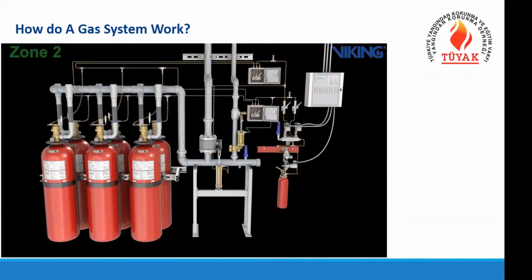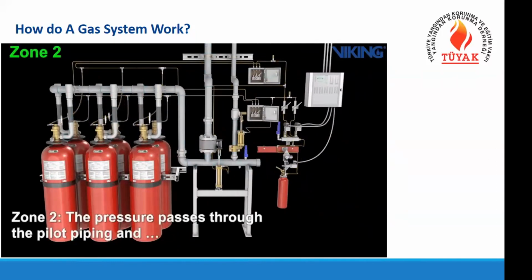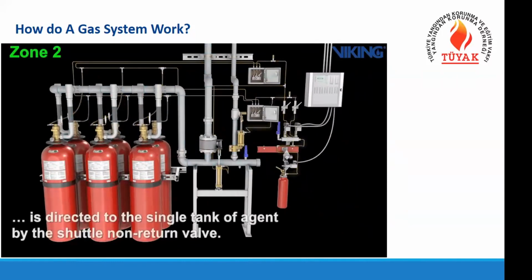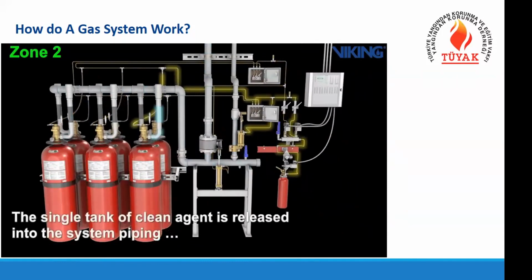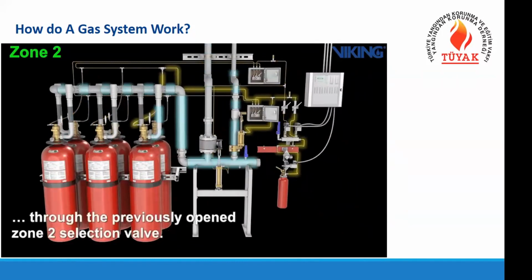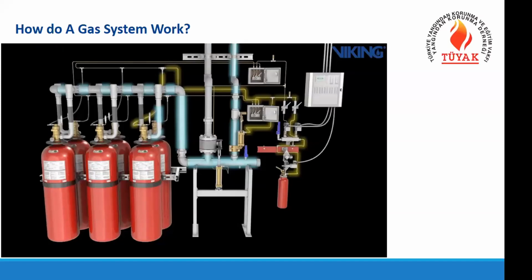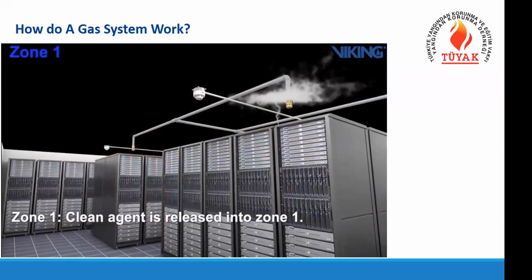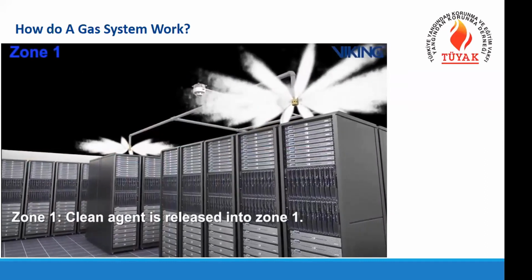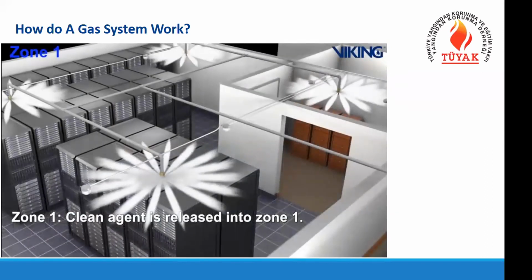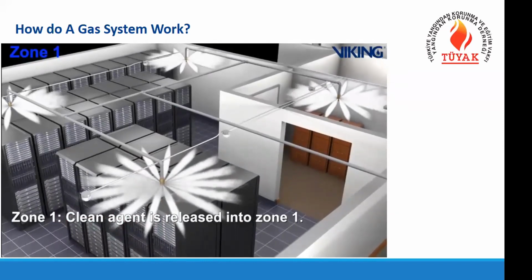Or otherwise, if it was zone 2, the related pilot line activates the necessary number of cylinders, which is this time not 3 but 1. So it's a very small room. So it sends all the gas from one cylinder to the room automatically. And as you see now, in zone 1 the gas is discharged to the room and controls the fire.